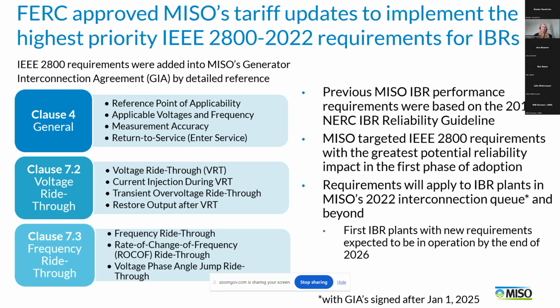And so that's where we could specify things like duration of the enter service period and some other details. The rest of the requirements were from clause 7, which of course is our main topic of discussion today. From subclause 7.2, we implemented requirements for voltage and transient overvoltage ride-through, as well as the requirements for current injection during voltage ride-through, and then restoration of active power output after voltage ride-through. And lastly, from clause 7.3, we pulled the requirements for frequency, rate of change of frequency (ROCOF), and phase angle jump ride-through.